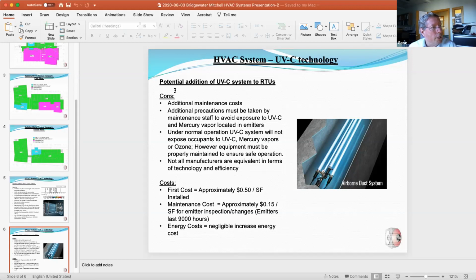And then if the committee wanted to consider a way to actually kill some of the airborne pathogens that get recycled through the system, this UV technology is probably the best to do. It's not going to kill all of the pathogens, but it will kill a fairly substantial percentage of them. The cost impact is about, I'm going to round, but I think around $75,000 in first costs. And then as Dom said, you'll have to change the bulbs maybe on a yearly basis. At 15 cents a square foot, I just did a quick calc, it might be around $20,000 a year in maintenance.